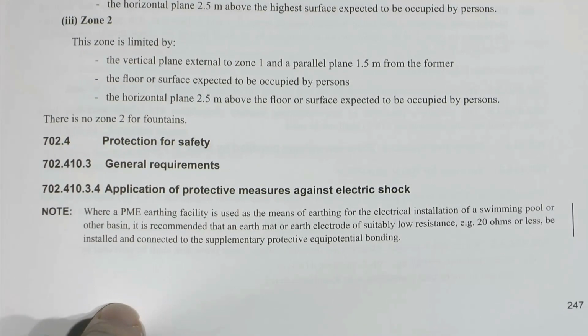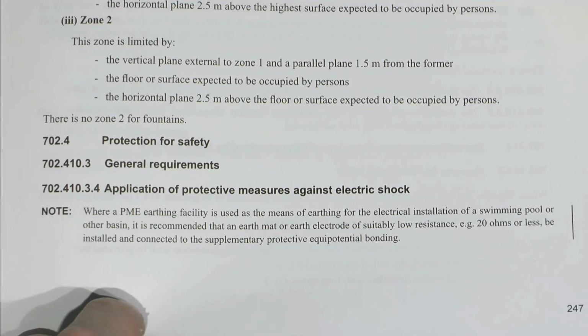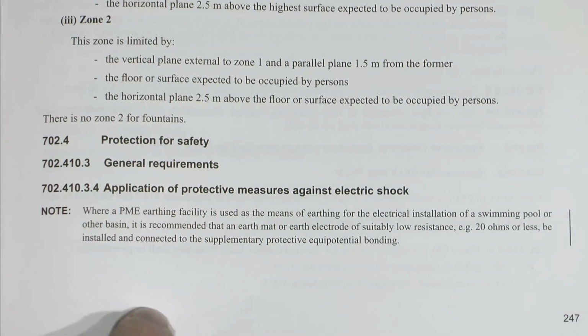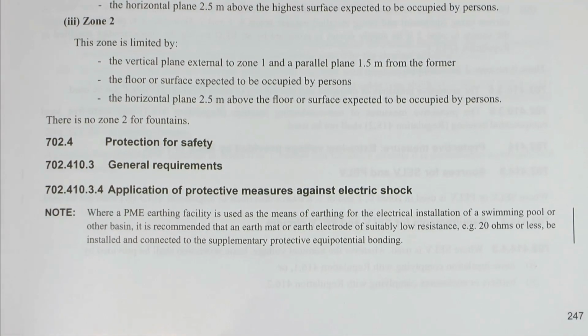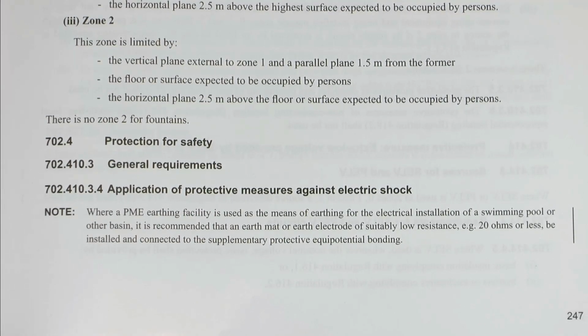Now one thing at the bottom here we've got in 702.410.3.4, application of protective measures against electric shock, we have this note, and this is where a PME earthing facility is used, and it's suggested that an earth mat or electrode of resistance 20 ohms or less be installed.